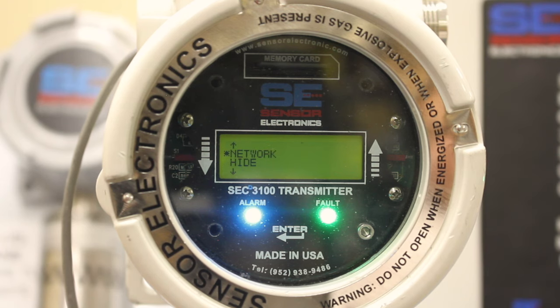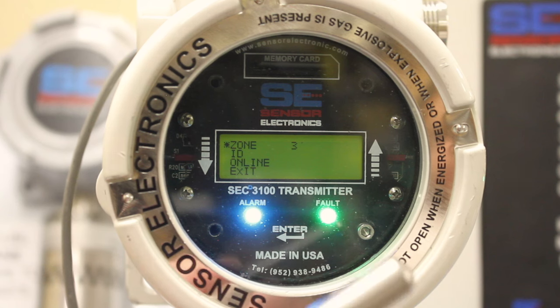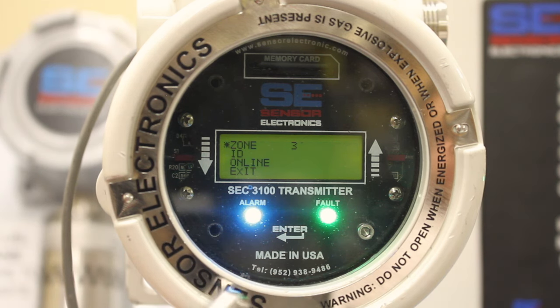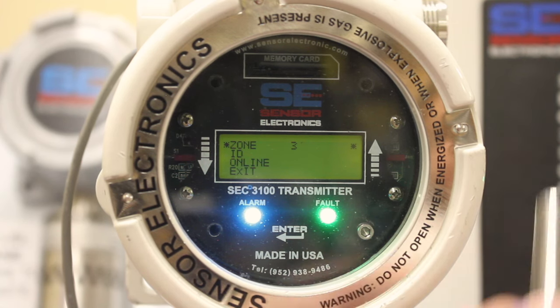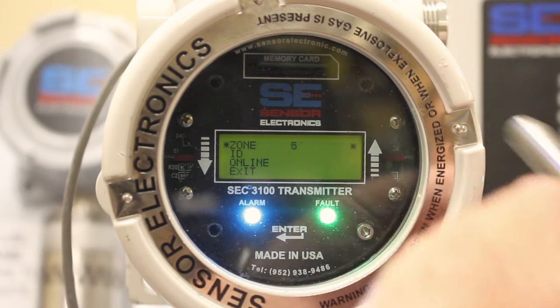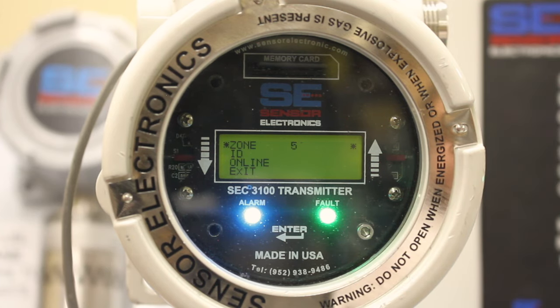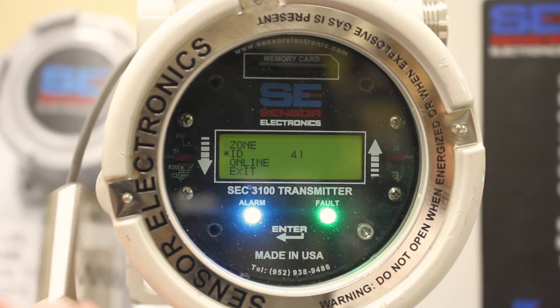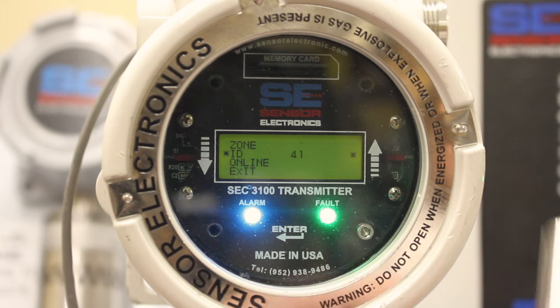The next menu is the network menu. What this allows you to do is change the zone of the transmitter head. So again, you just select enter, go up or down to whatever zone you want the transmitter to be located in. You can also change the ID of the sensor. So you select enter and use the up down arrows to change the ID. Once you have the correct ID selected, select enter.